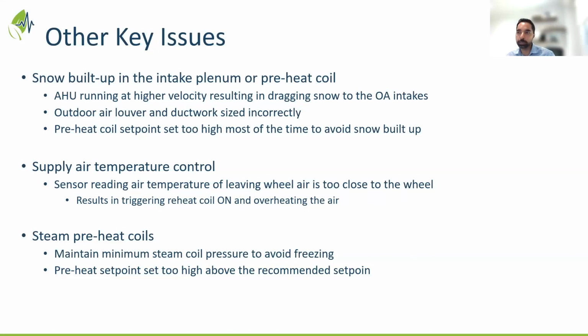I don't know what that is, but it could be additional space for your outside air plenum, so you get enough space for snow accumulation in the plenum, and then you have your systems next to it. So that, as to your point, maybe an extended ductwork would make sure that you don't keep pulling the air with the snow into your system, which is sitting next to your outside air plenum.